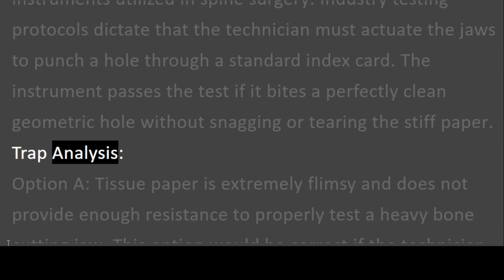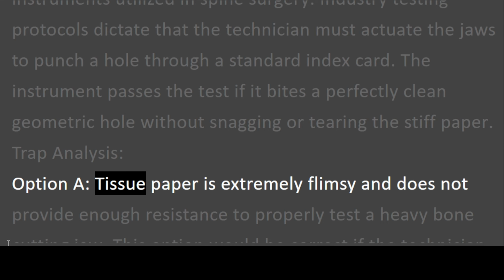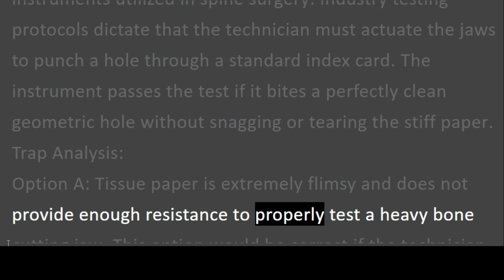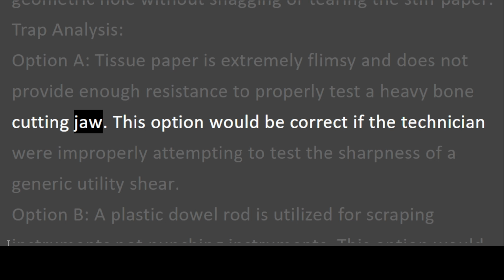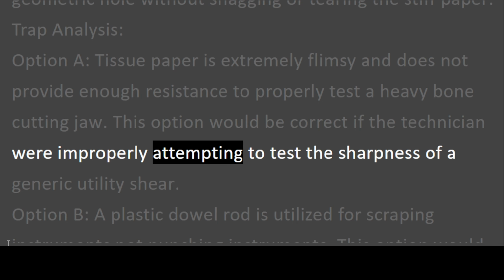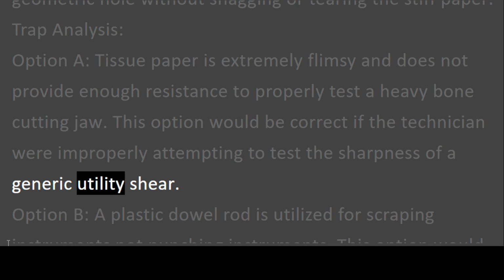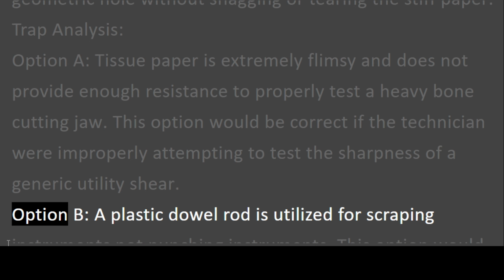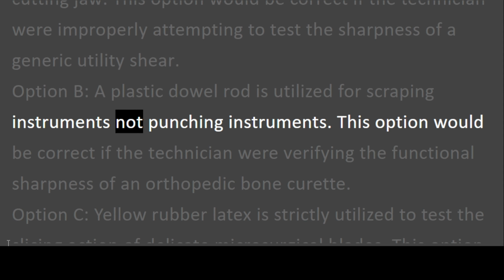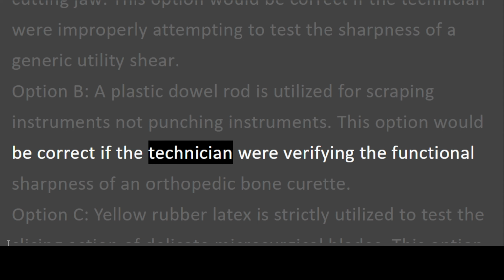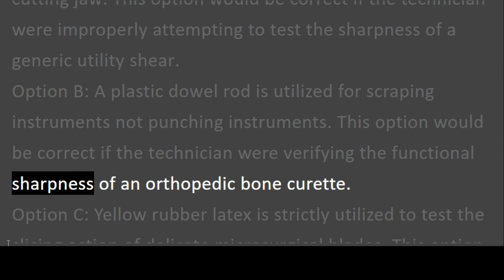Trap analysis. Option A. Tissue paper is extremely flimsy and does not provide enough resistance to properly test a heavy bone-cutting jaw. This option would be correct if the technician were improperly attempting to test the sharpness of a generic utility shear. Option B. A plastic dowel rod is utilized for scraping instruments, not punching instruments. This option would be correct if the technician were verifying the functional sharpness of an orthopedic bone curette.